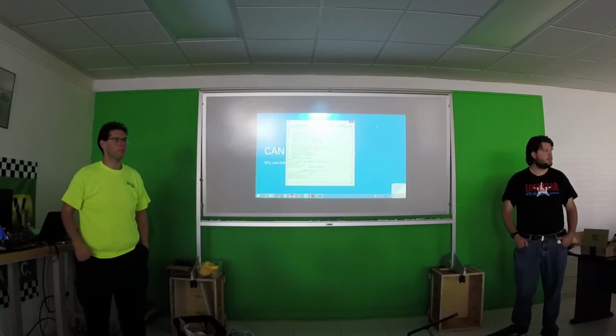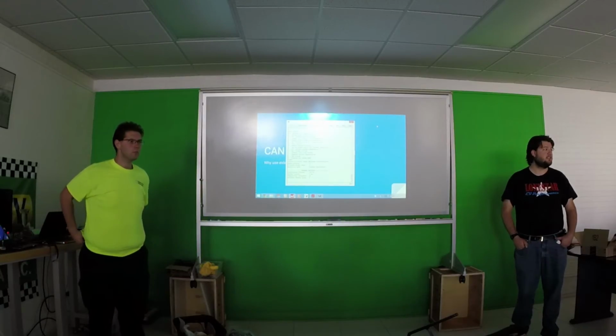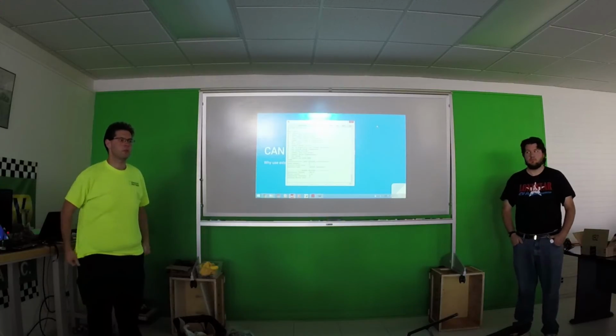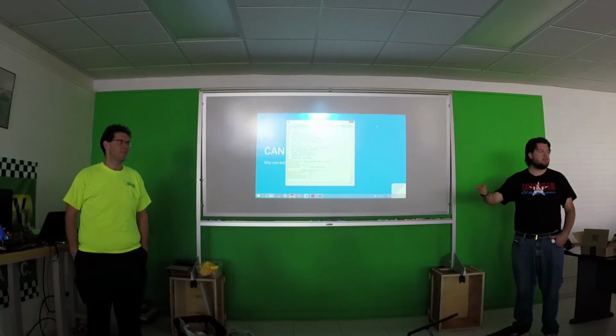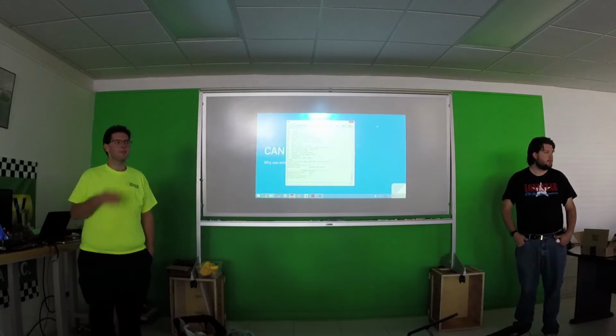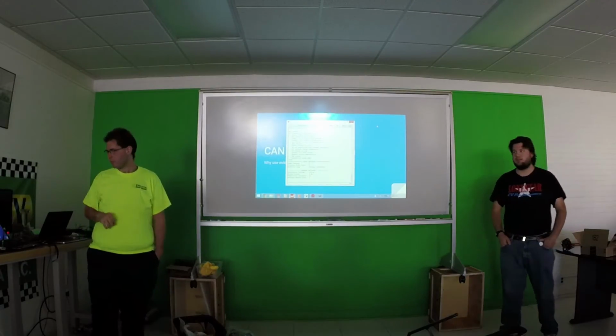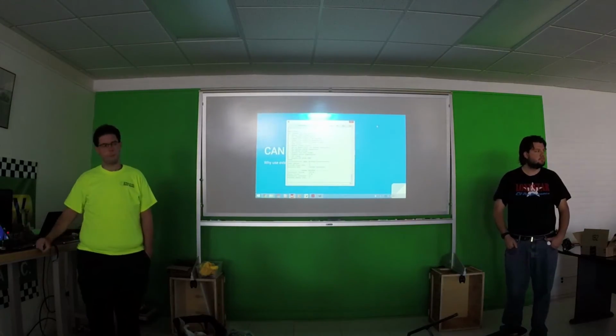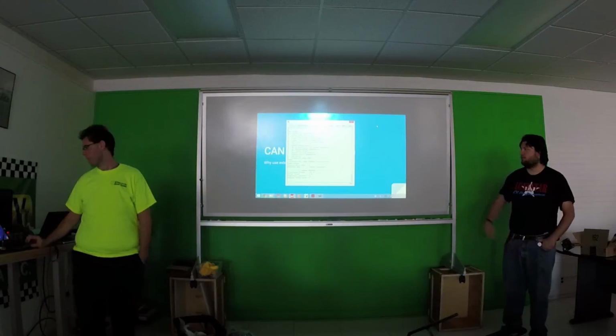250K, yeah, this is hard coded at 250K baud because that's what the EVCON is. I understand. Could be changed. It's software. How could it be changed? Well, we could put different firmware on this to run at a different baud rate. But it's not configurable. No, not configurable. Okay. Again, with the purpose that this was built for. And what's the CAN bus address, or can you configure that? So, we'll get to the messaging structure.